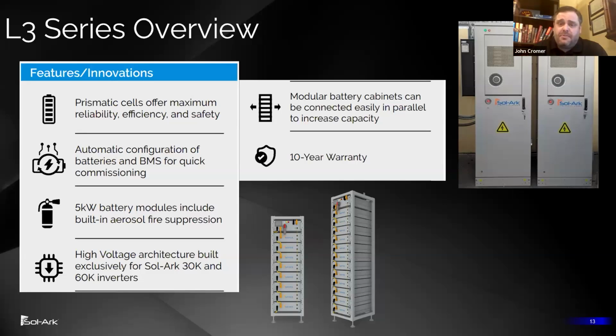We choose to keep it simple with air cooling for these smaller systems, so that you don't have the possibility of the liquid cooling glycol failing and filling up the cabinet with vapor, causing an arc fault, or in the case of the Moss battery plant facility fire that occurred about a month ago, giant containerized fire in California. That was caused, I believe, from a leaky water cooling system. And because we have the fire suppression built in, you can exempt yourself from those requirements and have a more simple and more reliable project. So prismatic cells, built-in fire suppression, very modular, and a 10-year warranty.